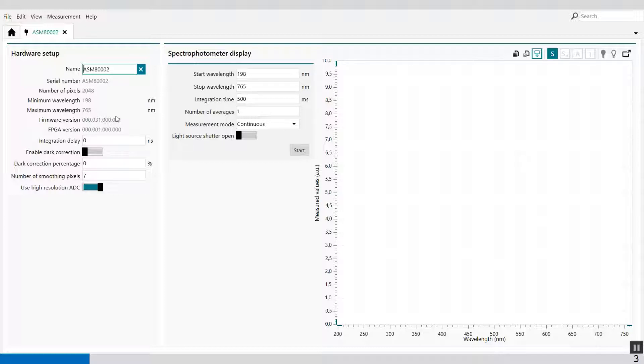Then we have the enable dark correction, a toggle which can be used to enable or disable the dark correction — by default it's off. The dark correction addresses the fact that the pixels of the CCD detector are thermally sensitive, which causes a small dark current even without exposure to light. The Autolab spectrophotometers are fitted with dedicated black pixels; to get an approximation of the dark current, these black pixels can be subtracted from the raw data. Since these optical black pixels have the same thermal behavior as the active pixels, the correction is dynamic. Enabling dark correction will therefore result in the baseline fluctuating around zero, and measurement data will be less sensitive to temperature changes than with dark correction disabled.